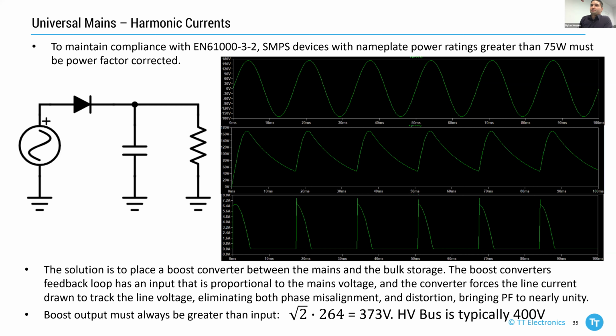I've drawn a really, really simplified schematic of the front end of an AC to DC converter, where we've got some AC source, some rectifier, which is typically going to be a full bridge rectifier, and then some giant bulk capacitance. So what happens here is as that capacitor charges up and develops some potential across it, we're going to start to have discontinuities in the current that flows from the AC source through that rectifier. If the voltage on the AC source falls below the voltage that's currently stored on the capacitor, no current is going to flow. So we're going to start to get a ton of harmonic content on our AC mains, and that causes dirty power, and so it needs to be regulated.